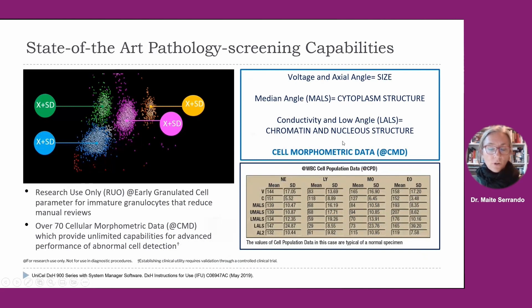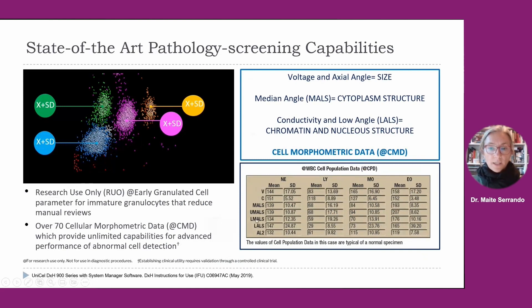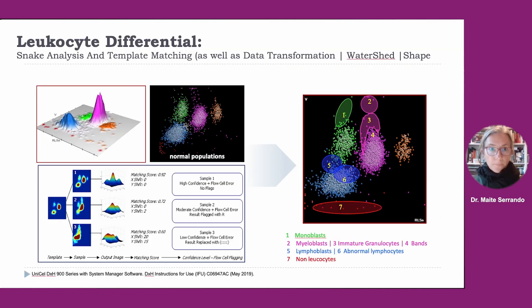All these combinations can be summarized in a table available on the DXH 900 screens. For each cluster of cells — neutrophils, lymphocytes, monocytes, and eosinophils — we have all these measurements with the mean and standard deviation for each cluster measured. For the leukocyte differential analysis, we have a combination of two algorithms: the snake analysis and template matching.